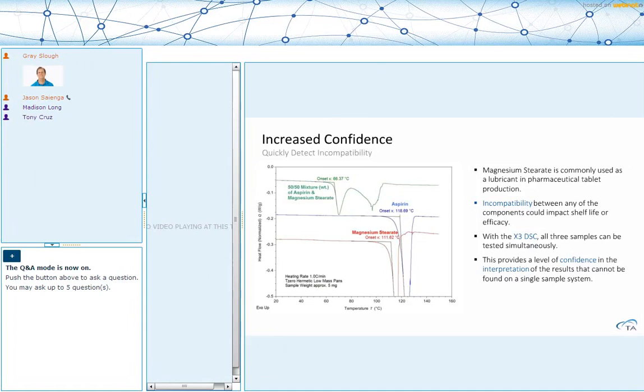If we look at another example here, this particular example is magnesium stearate and aspirin, and then a mixture of the 2. Magnesium stearate is commonly used as a lubricant in pharmaceutical materials, but it could be any 2 materials. Investigating the compatibility or incompatibility between materials typically requires some understanding of what the raw materials are going to do independent of the mixture. And so here we don't have to run 3 separate experiments to get an idea that this mixture of the magnesium stearate and the aspirin is incompatible, thus showing us 2 separate peaks in the heat flow rather than 2 independent peaks associated with the magnesium stearate and the aspirin.